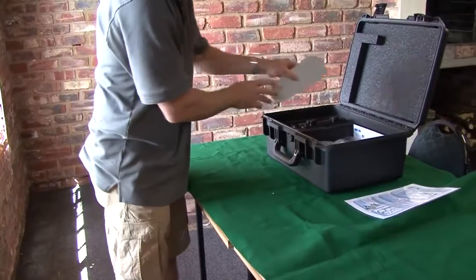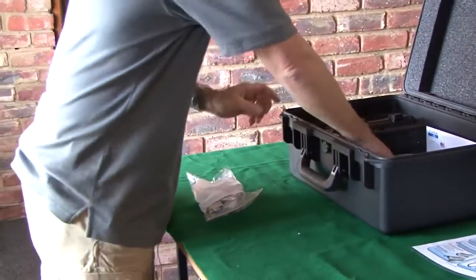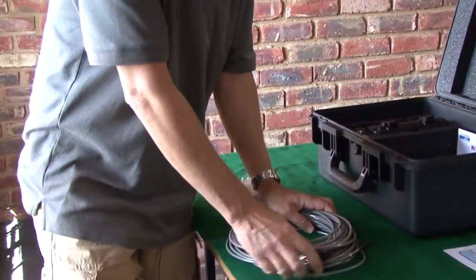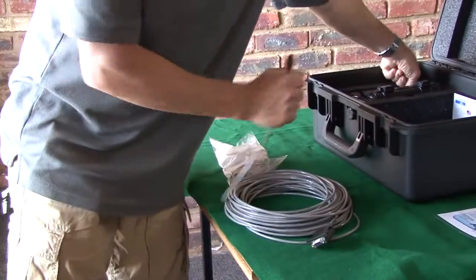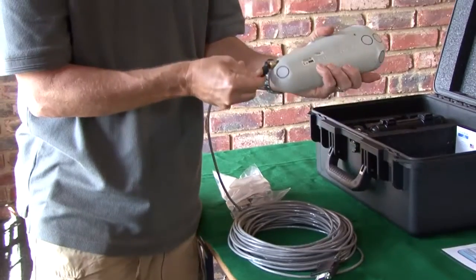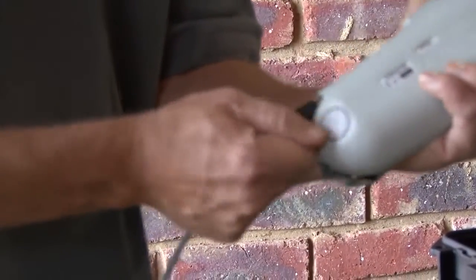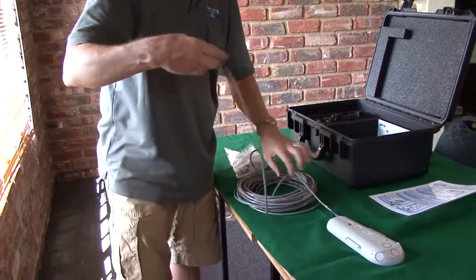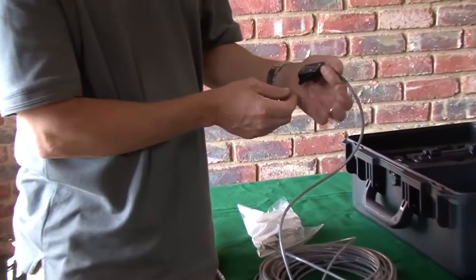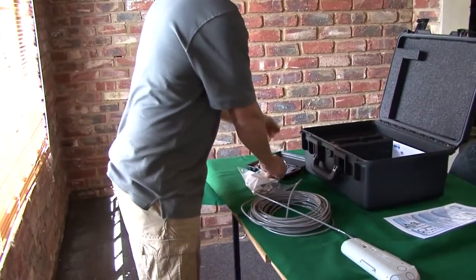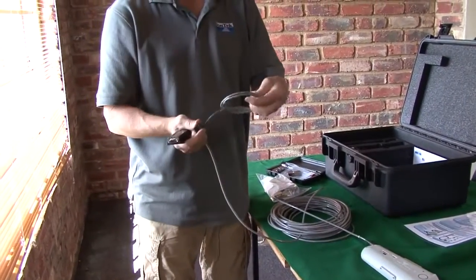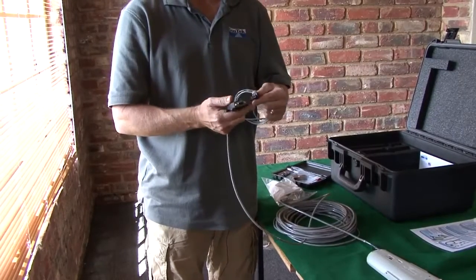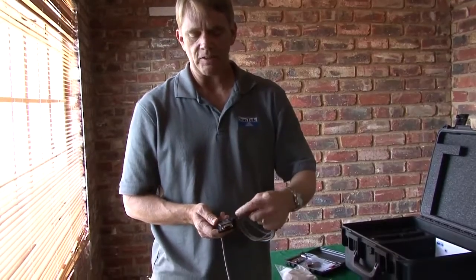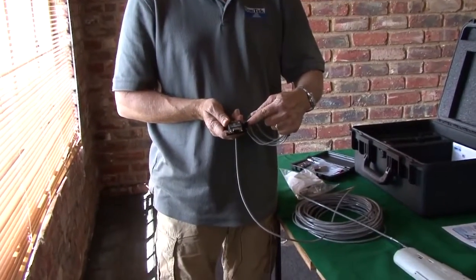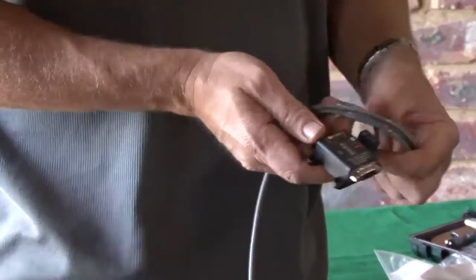Of course, every instrument like this comes with a variety of cables and connections. Your IQ should arrive with a power and communications cable. This is the cable. I'll just show you quickly here. This plugs into the IQ, and this is the side that goes into your shelter. Here's the power connector right here. You plug that in right there. Depending upon how you connect power to it, I have a little power cable here. It operates between 7 and 14 volts, and I can plug it in there. This also provides the SDI line if I'm using an SDI 12 data logger. Everything's pretty well marked.